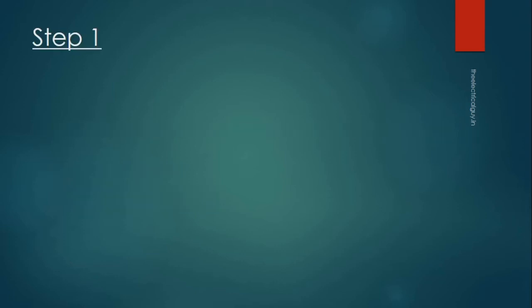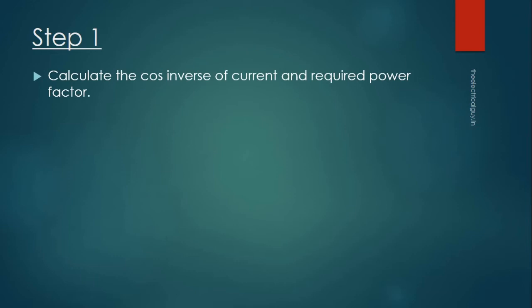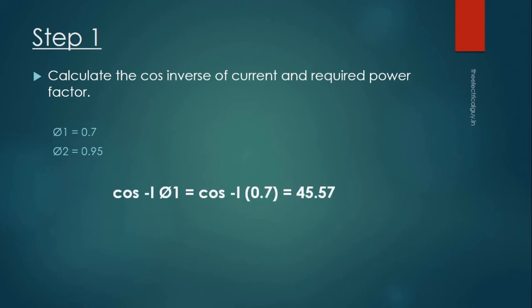Step 1: Calculate the cos inverse of current and required power factor. Now in our case current power factor is 0.7 and required power factor is 0.95. So the cos inverse of φ1 is 45.57 and φ2 is 18.19.